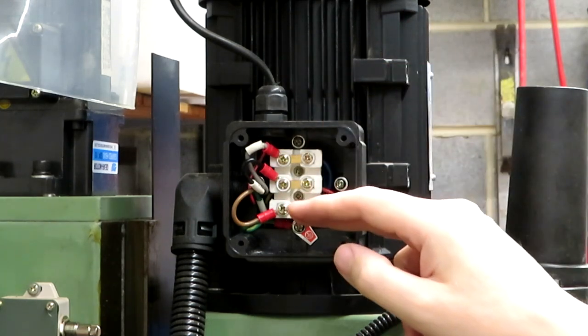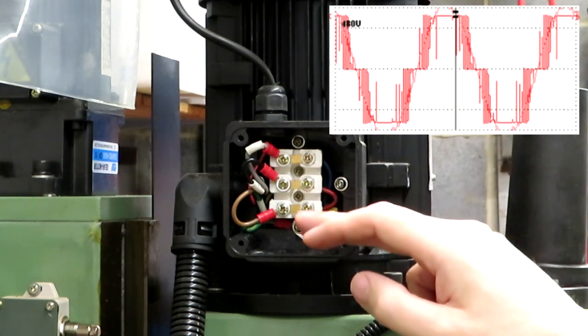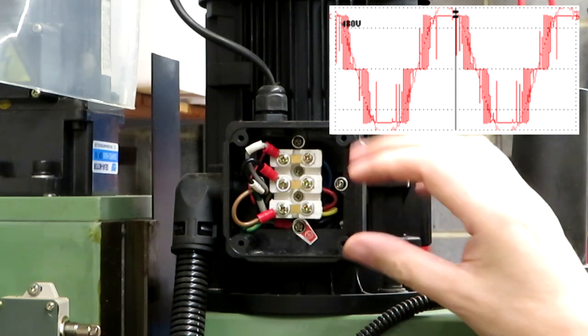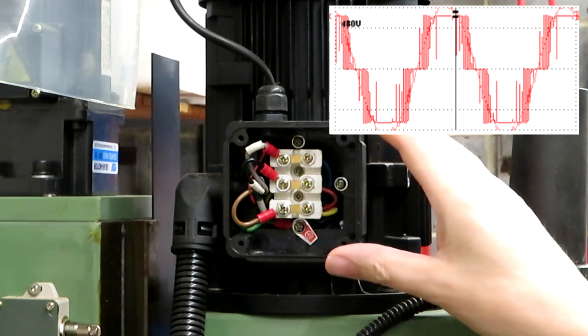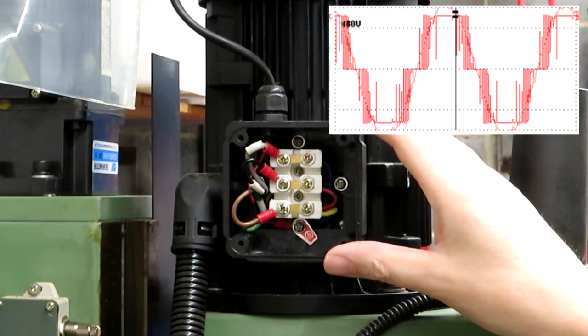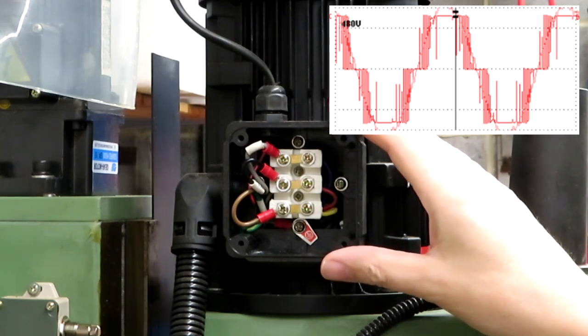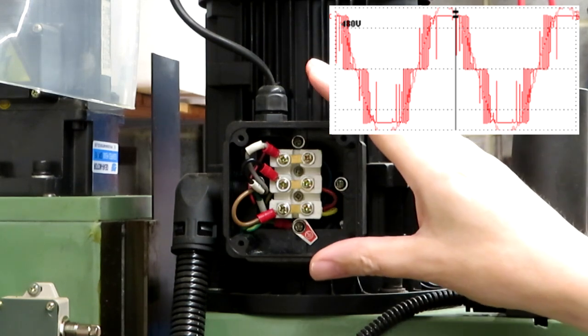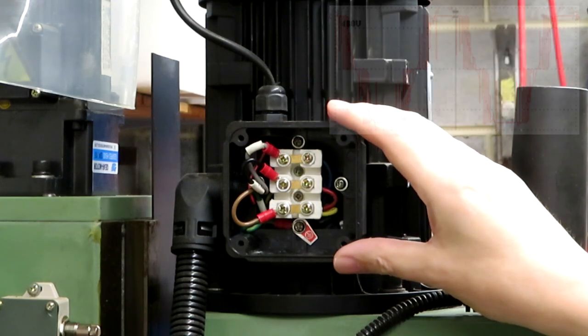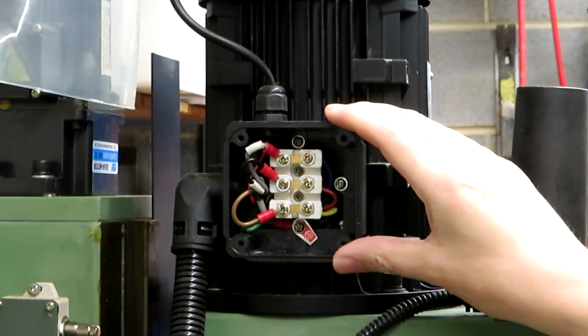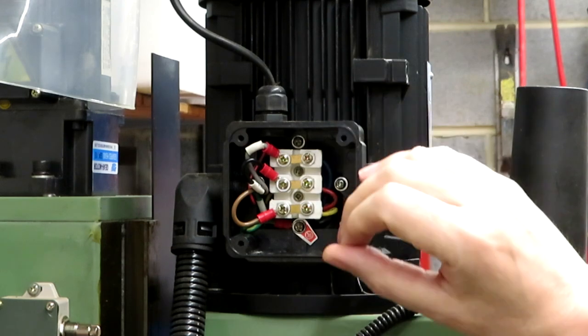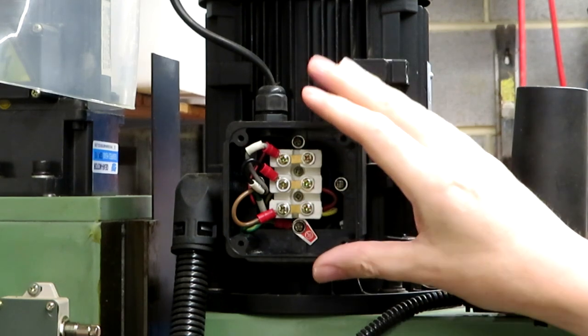Now, if we were to have a look at the voltage waveforms with an oscilloscope, what we'd find is that they wouldn't be sinusoidal like we're used to looking at. They would be closer to being some kind of square wave shape, and that's because the way that a VFD works, it takes the incoming mains supply, it rectifies it, and then it chops it up again, and it supplies that chopped up DC to the motor.